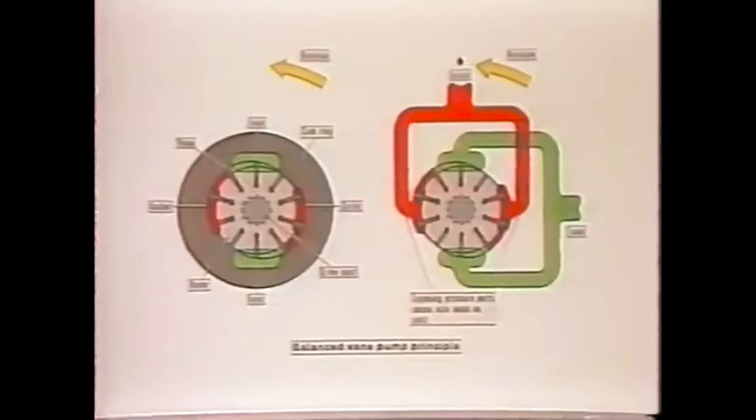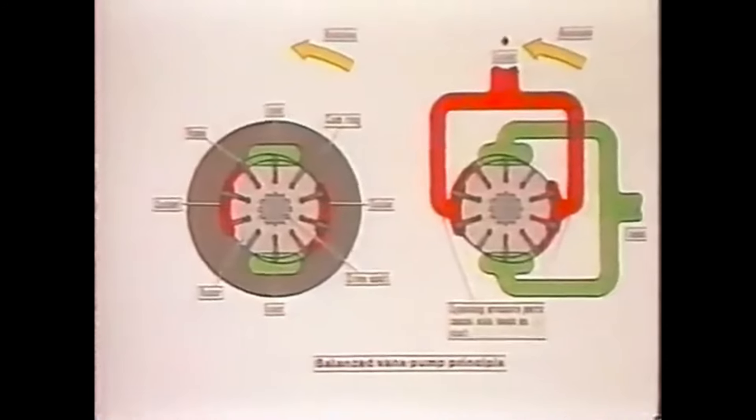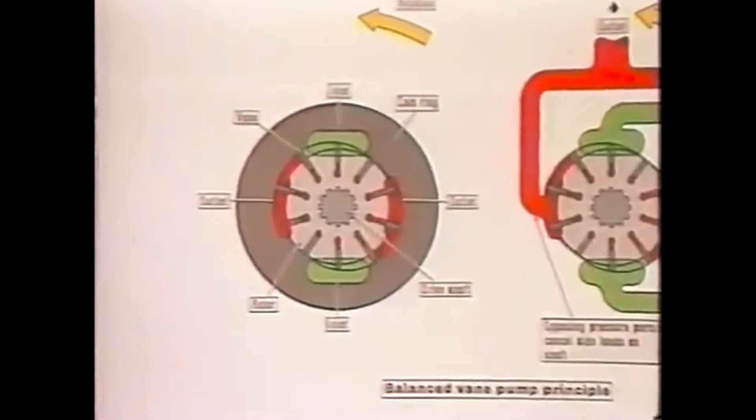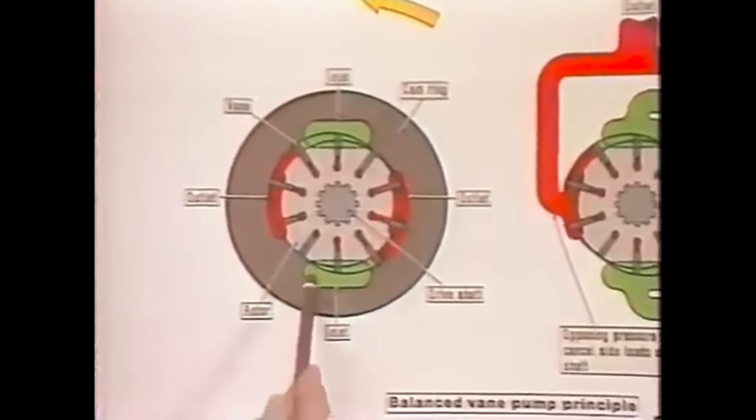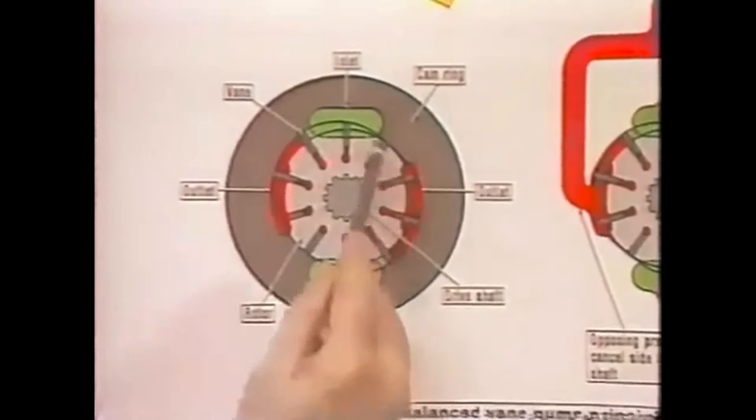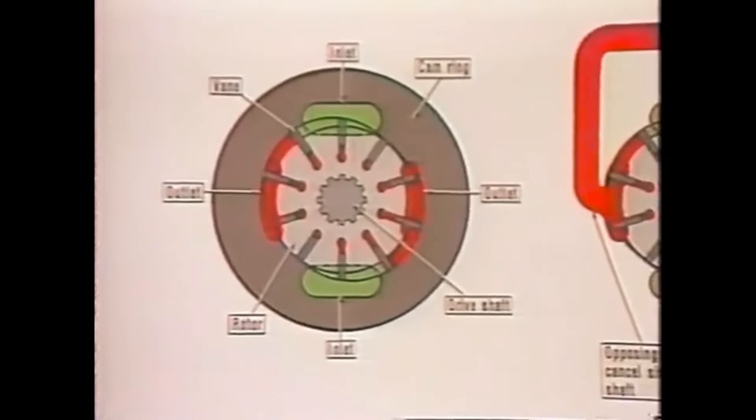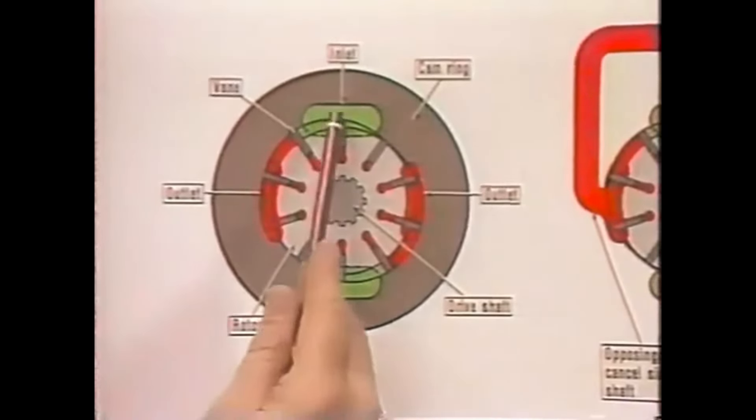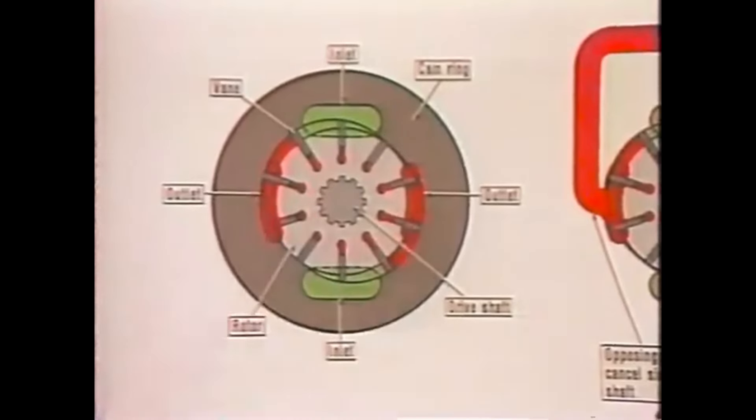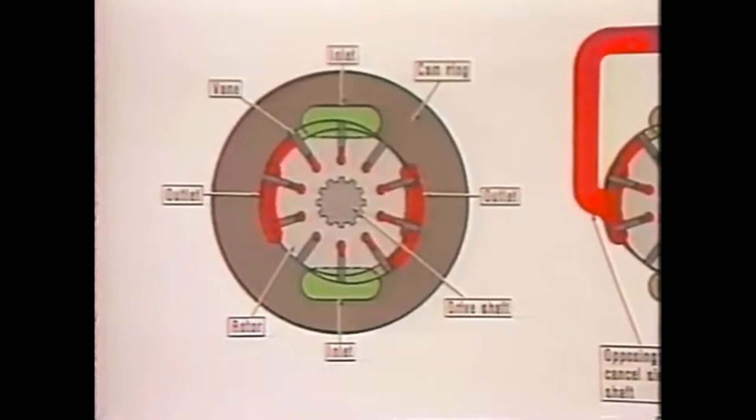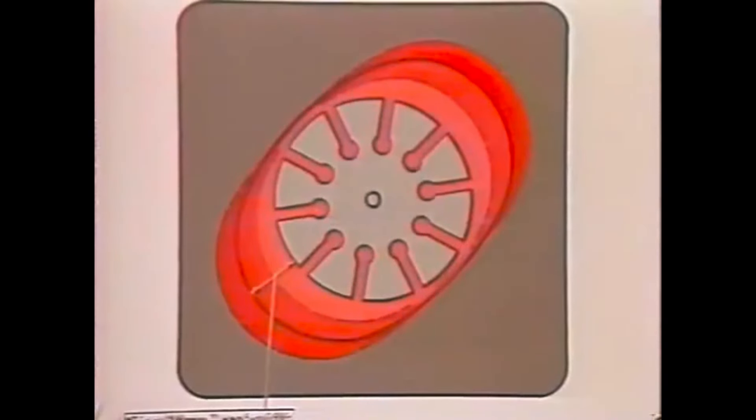Now, a balanced vane pump operates in the same manner as an unbalanced unit, the difference being that the inner contour of the ring is an ellipse rather than a circle. This configuration forms two sets of pumping chambers. They're on opposite sides of the rotor but are interconnected through passages within the housing. Forces caused by pressure buildup on one side are canceled out by equal but opposite forces on the other. The displacement of a balanced design vane pump cannot be adjusted.